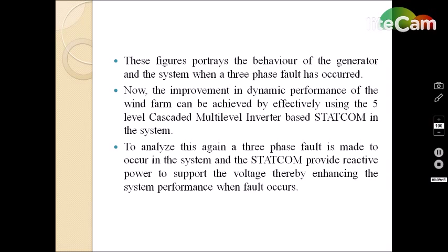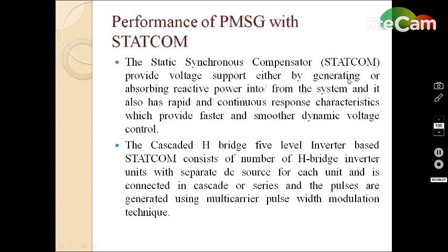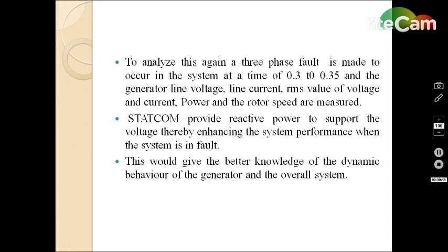As I told before, the STATCOM will improve the performance of your system by generating or absorbing reactive power into or from the system, and it has rapid and continuous response characteristics which provide faster and smoother dynamic voltage control. And here we have used a cascaded H-bridge 5-level inverter based STATCOM. Again we have induced a fault at the time period of 0.3 to 0.35 in the same transmission line, and it will provide voltage support to the system. This simulation output will give better knowledge of the dynamic behavior of the generator and the overall system performance.